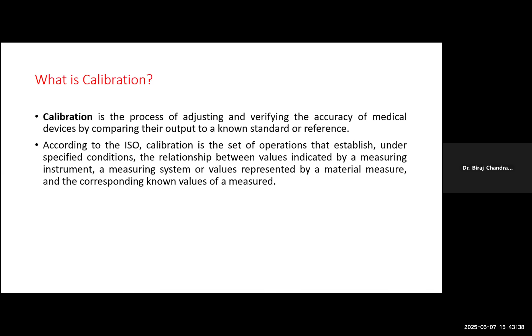So calibration is not a one-time procedure. You have to do it, maybe 6 monthly or yearly. There are so many factors, but we recommend following the manufacturer's recommendations and also NABL 126 or IPHS 2022. Why is calibration critical?